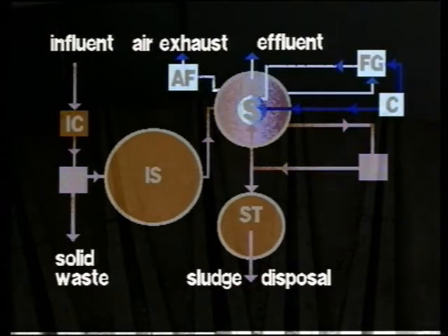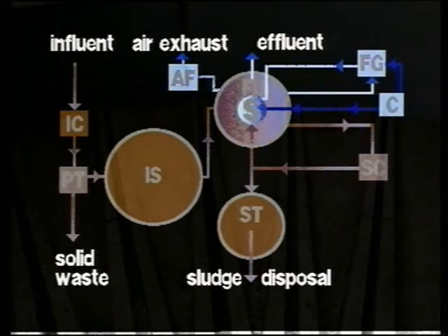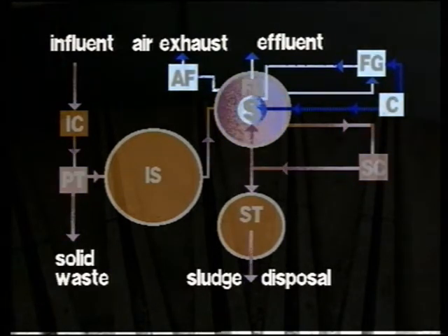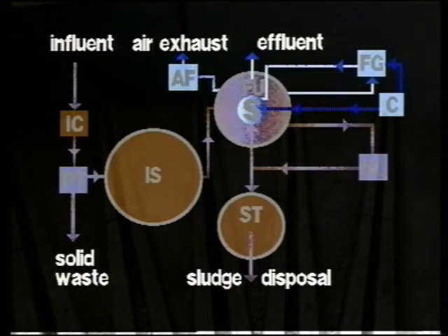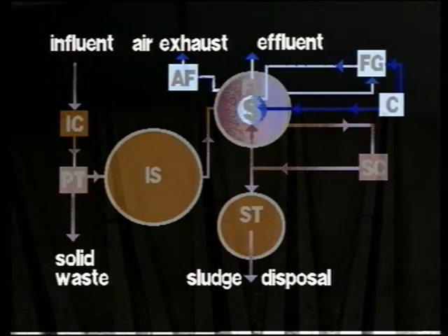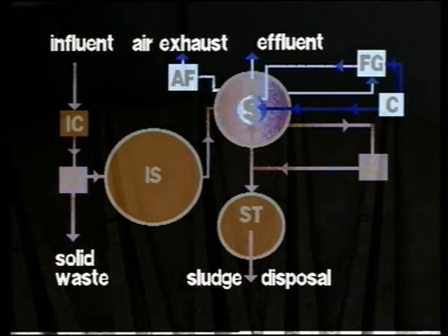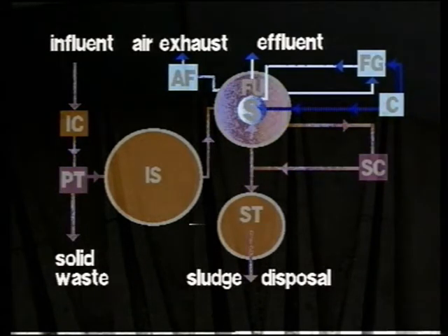Descending toward the bottom of the shaft, the effluent sludge mixes with air being injected under pressure at the bottom of the shaft, where the purification process really commences. As opposed to sedimentation, flotation is an active process, and the multi-reactor flotation process requires very little energy as a result of the required volume of air bubbles being released from the water in the aeration shaft.